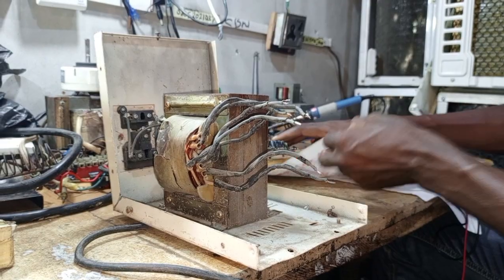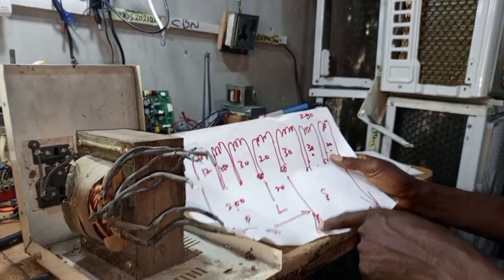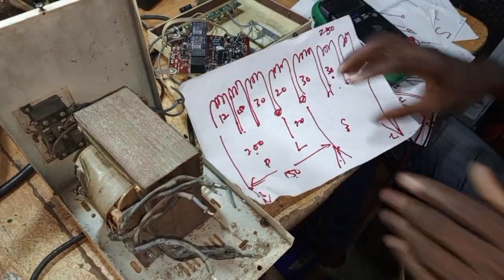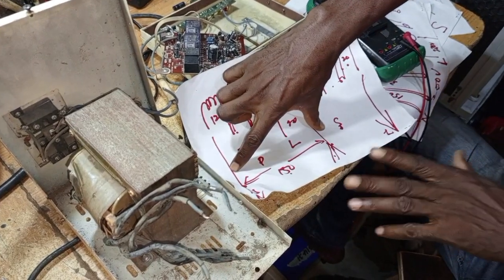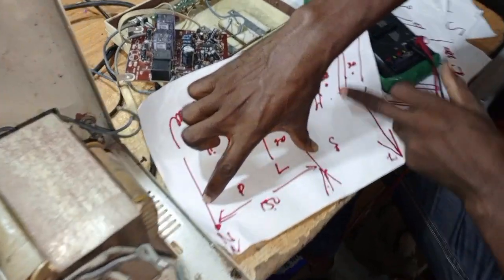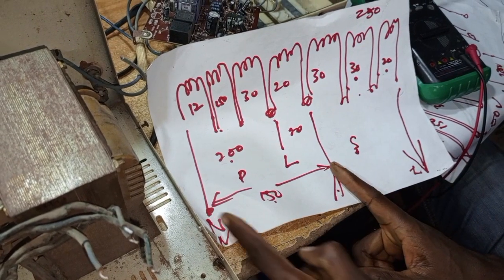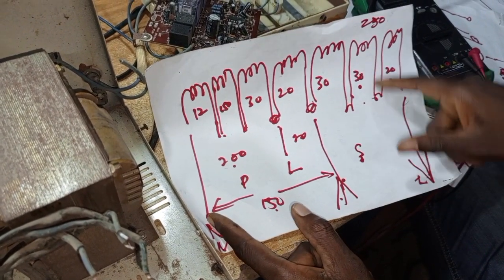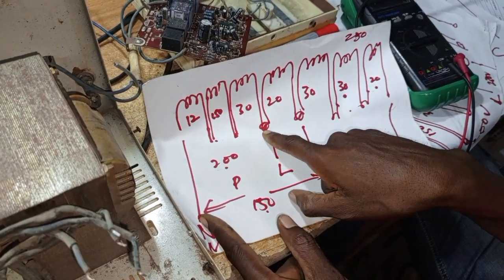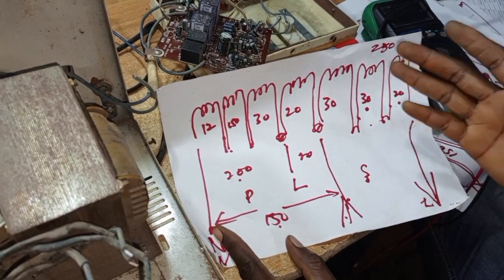Like I explained using this diagram, let's assume I feed in 150 volts — which is my primary, here and here. My secondary I take from this neutral to the last line, to any of these tappings, depending on the voltage I want. From here to here is my primary. From here to any of these tappings is my secondary. And I can even come before here to take my secondary — it does not matter. That's how I use it to set the stabilizer.